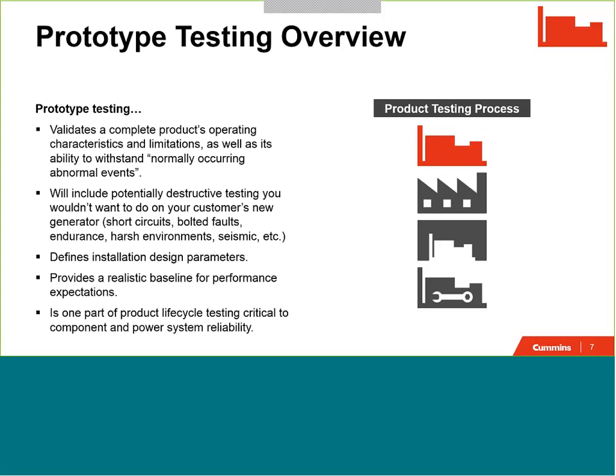Prototype testing also works to define installation design parameters. And what I mean by this is that prototype testing is what helps the manufacturer to establish the operating parameters of the particular product. It also provides a realistic baseline for performance expectations. And again, by that I mean that some testing will help us to establish a range of acceptable performance limitations that should be seen with a product that's configured for a specific project. Lastly, and you'll hear me say this a few times, prototype testing is just one part of the product life cycle, the product testing life cycle, and it is critical to the reliability of the power system.